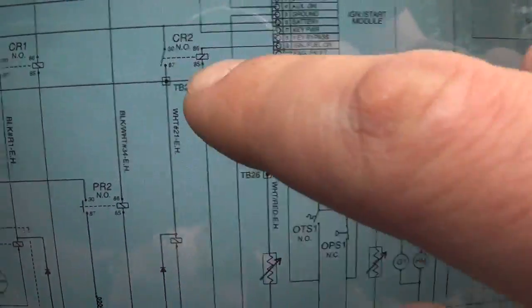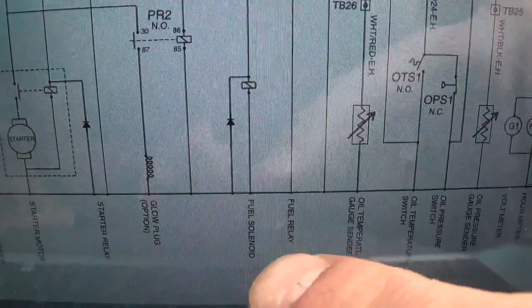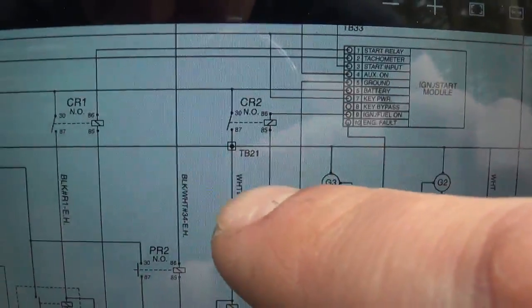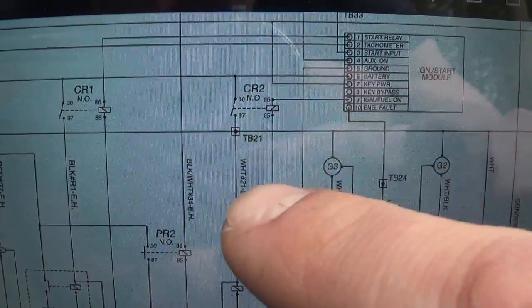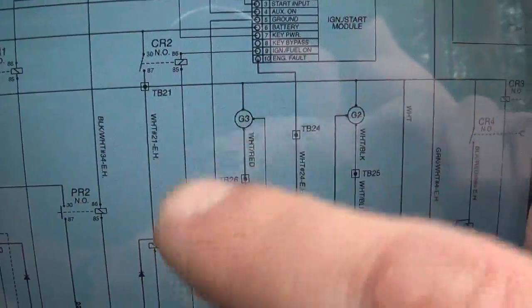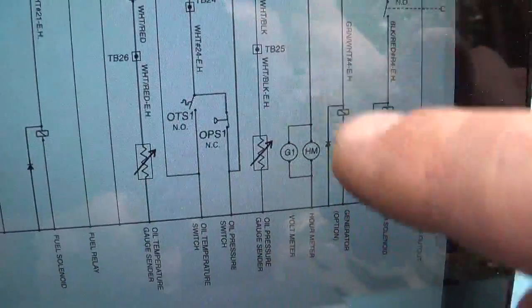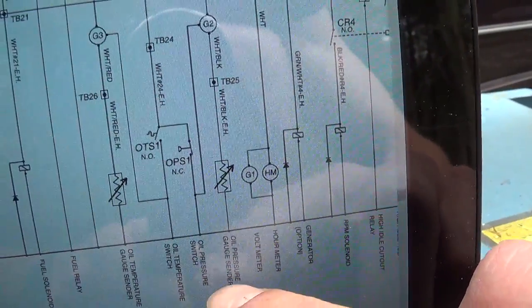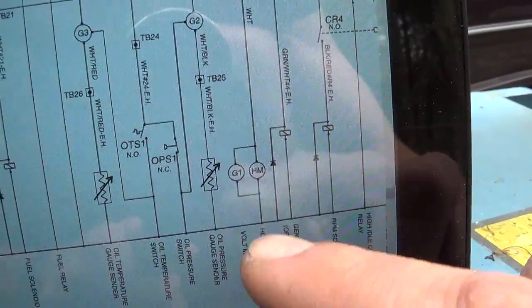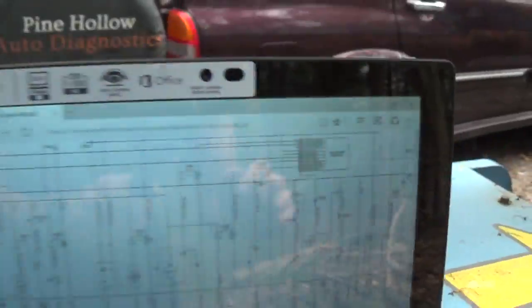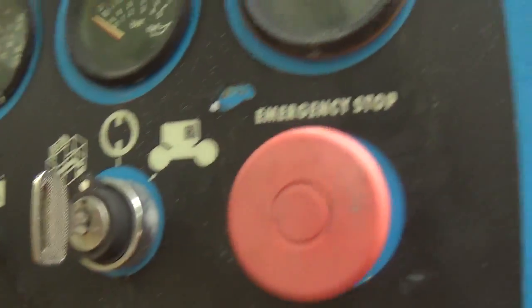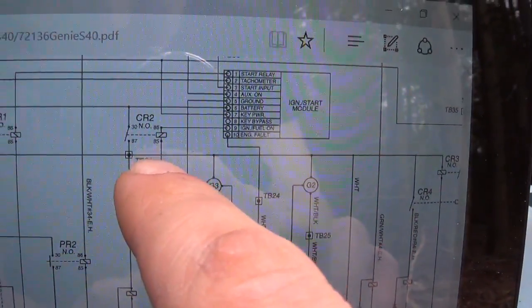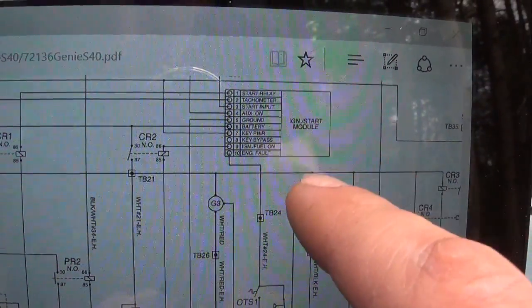And judging by the symptoms, see this relay right here? It says fuel solenoid. So when this relay clicks on, it powers up pretty much everything - the fuel solenoid, our oil pressure switch, voltmeter. So as you saw, the voltmeter, when this thing shut off, the voltmeter turned off basically, LED number 9 went off. So it seems to me that this relay right here is being intentionally shut down by the ignition start module.